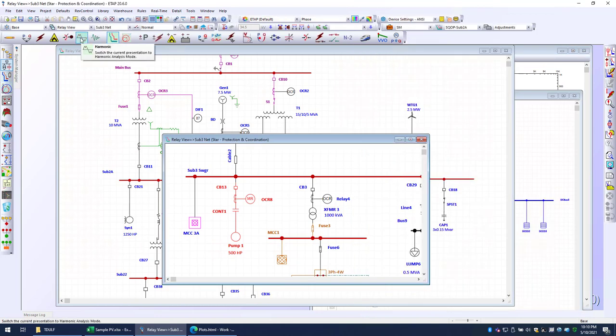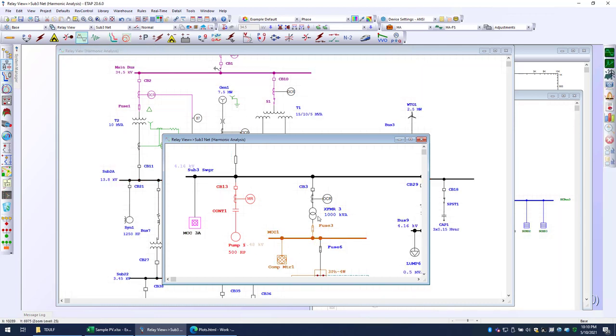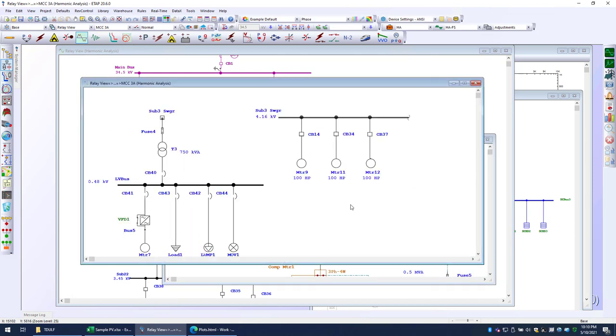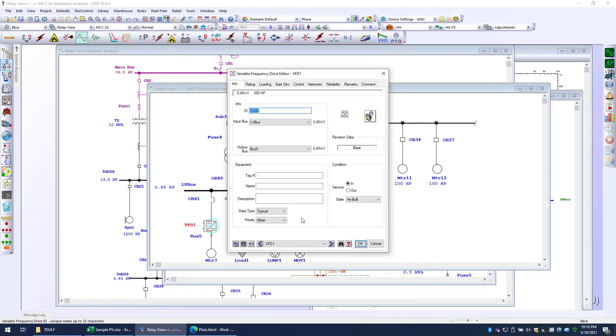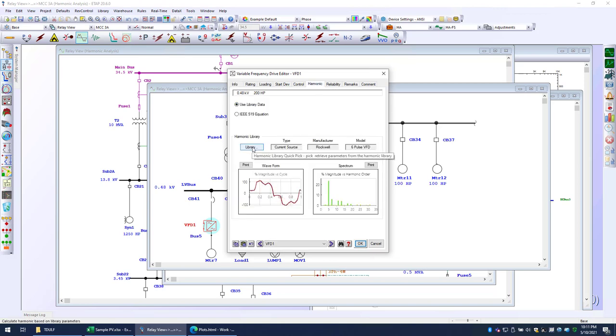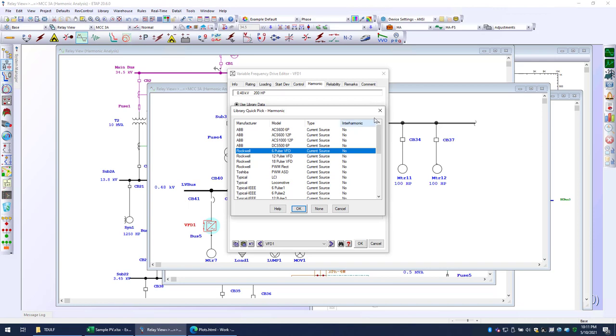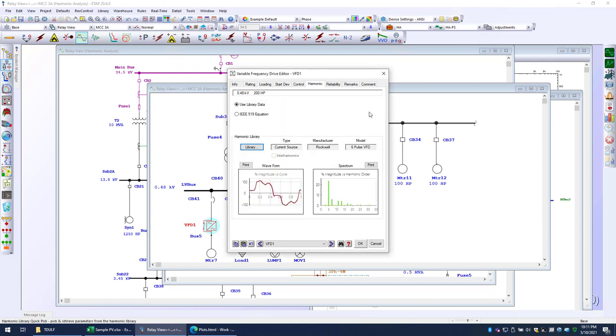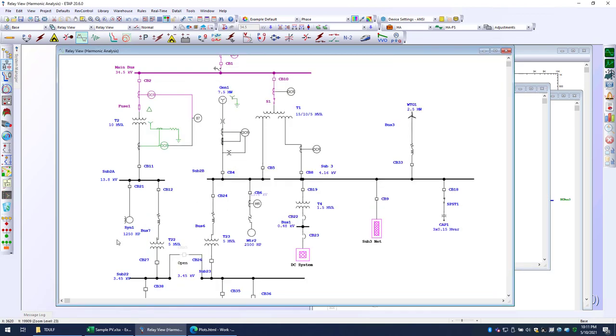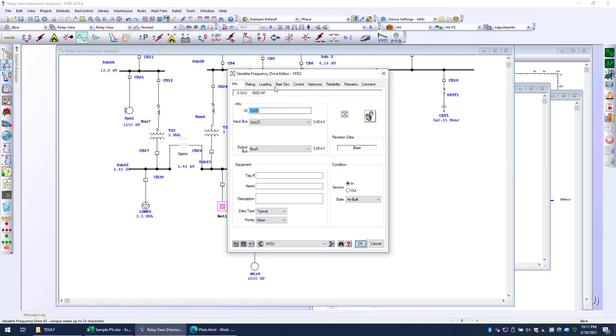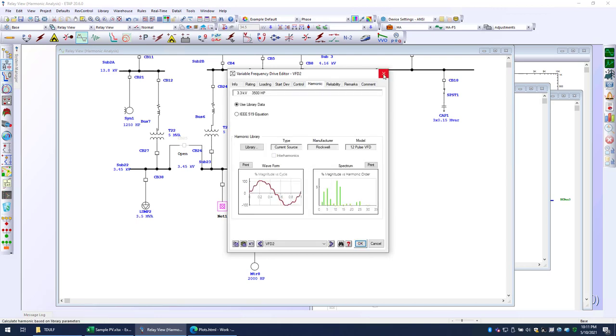So I'm going to switch over to harmonic analysis and just show you how easy it is to enter, for example, harmonic sources to a VFD drive. So I found a VFD drive here on my system. I head over to harmonic analysis, and you'll notice that the library is very comprehensive, with both manufacturer-provided source information as well as IEEE typical 6, 12, 18 pulse. So once you have, here's another variable speed drive. There's the harmonic source. It's a 12 pulse VFD.